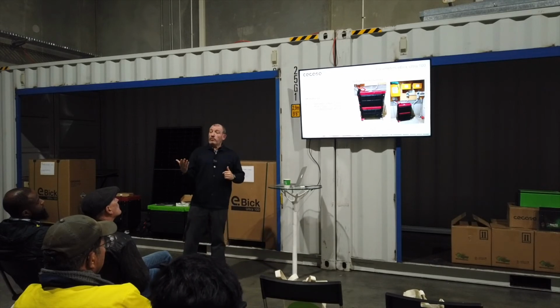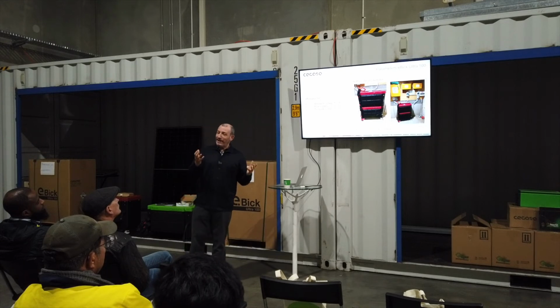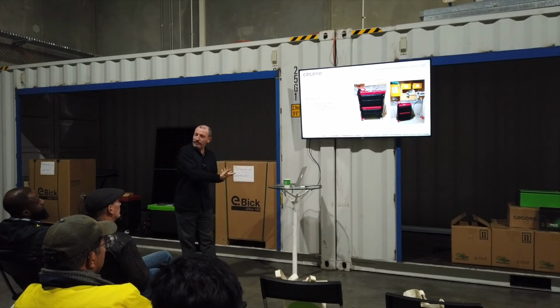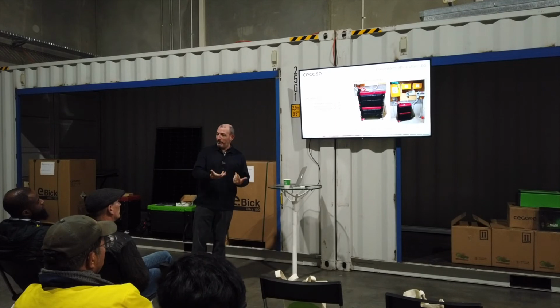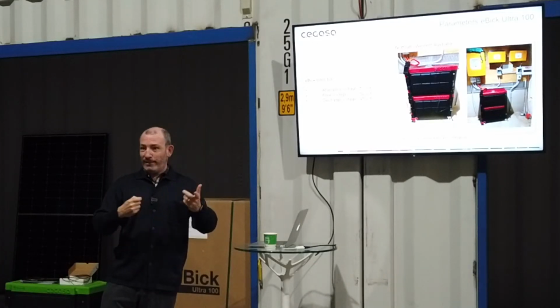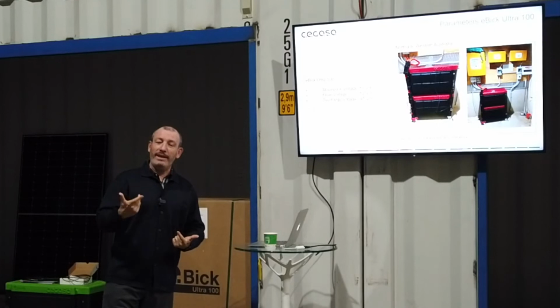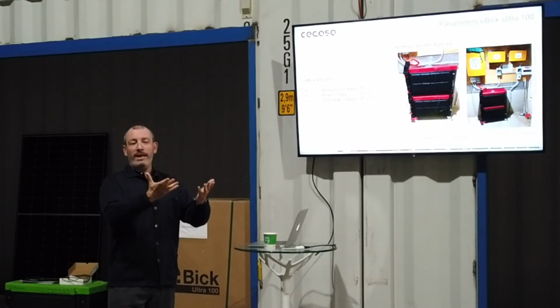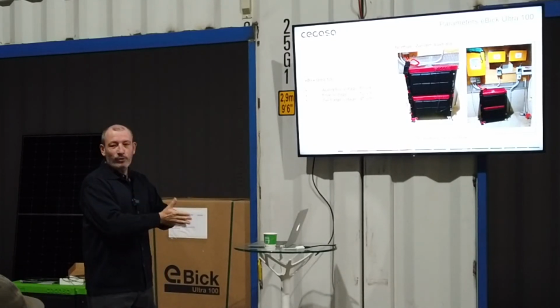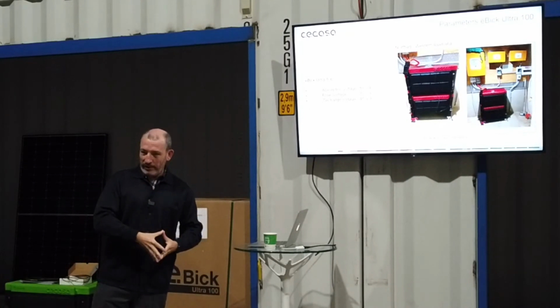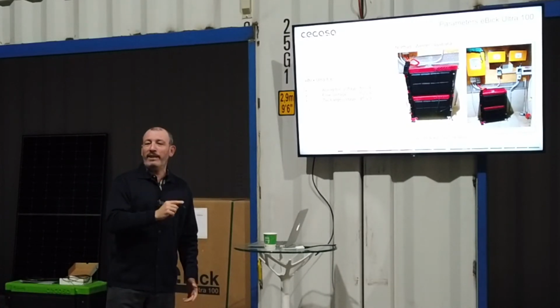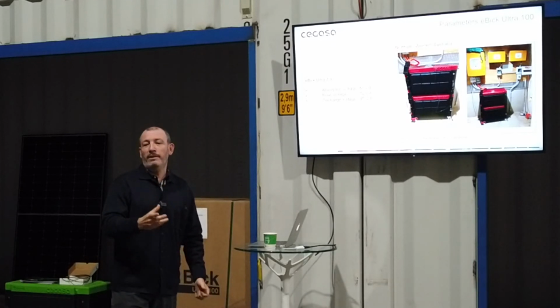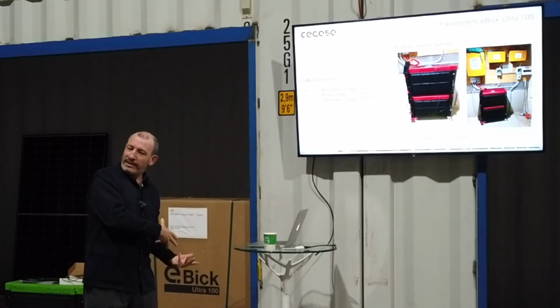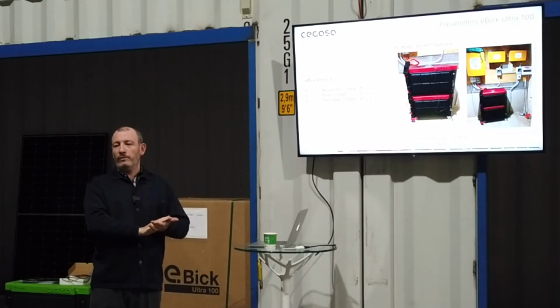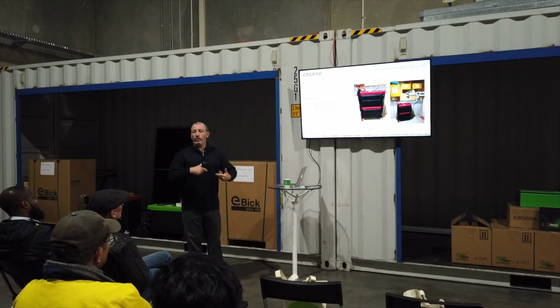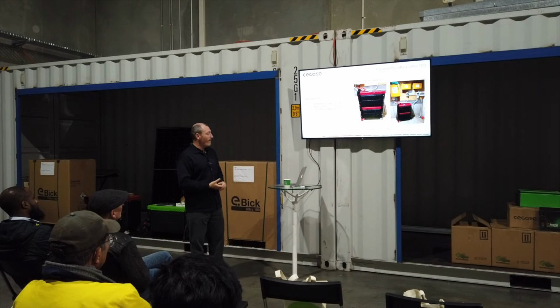It is true that we had some issues when, considering how easy it should be, we had installers asking, okay, this is not working properly, what is happening? Again, I remind you, it has to be set as a lead-acid battery. That's the first mistake that we commit. Because it's lithium, we put lithium, but no, we are treating it as a lead-acid battery. So the option you have to choose is lead-acid, and then is when you introduce the values.